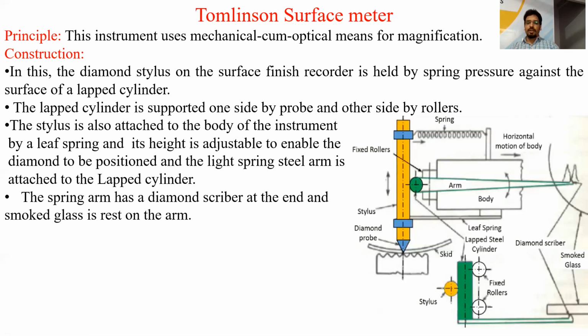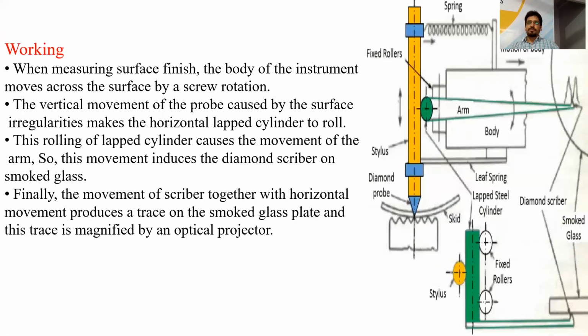Now we will talk about the working of the Tomlinson surface meter. When we have to measure the surface finish of any surface, we have to put the stylus with the diamond probe on the surface which is to be measured. When measuring surface finish, the body of the instrument moves across the surface by a screw rotation. The diamond probe of the stylus is in contact with the surface and it has to be moved by horizontal motion of the body. So the total instrument has to be moved over this surface whose roughness is to be measured.